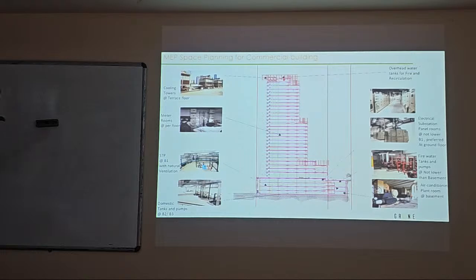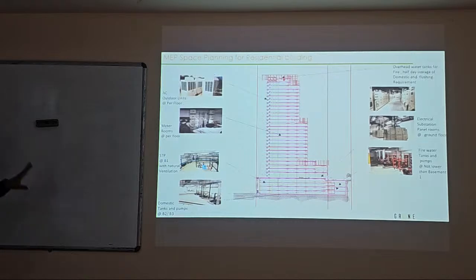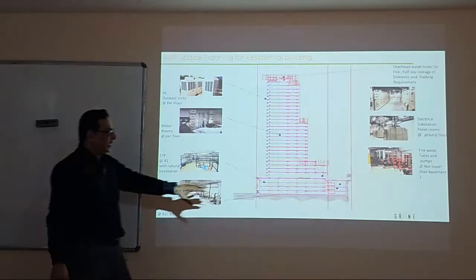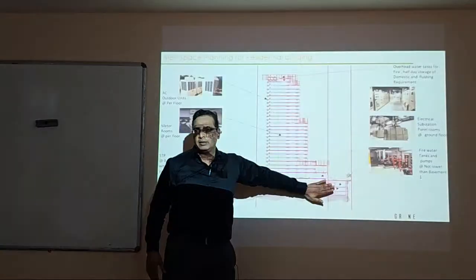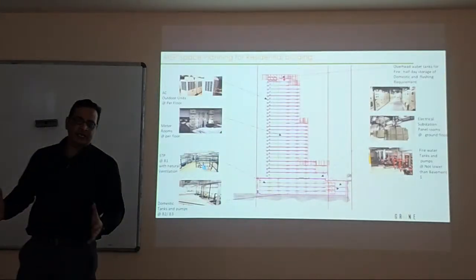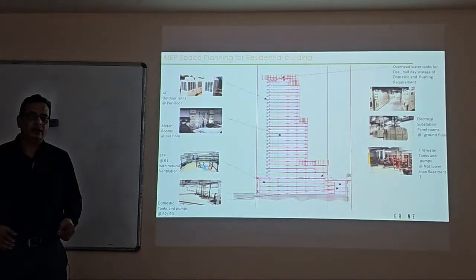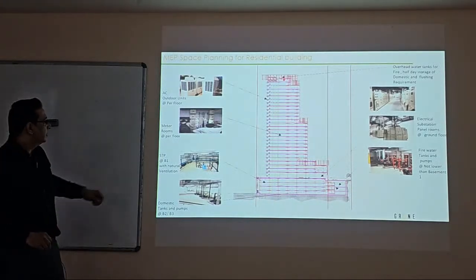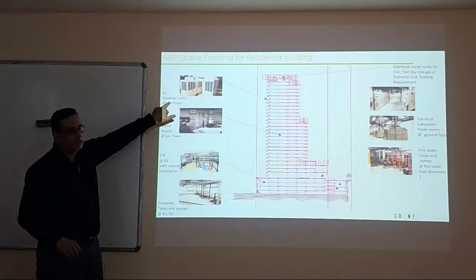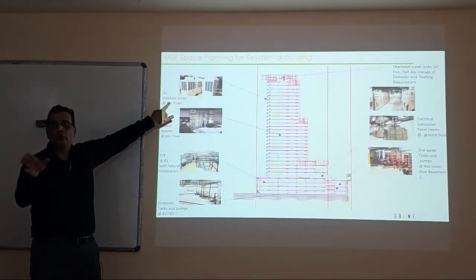What changes in a residential building? Everything remains the same, except the air conditioning plant room is removed since there's no central air conditioning plant room in a residential building. Instead, you need to plan space for the ODUs, the outdoor units.